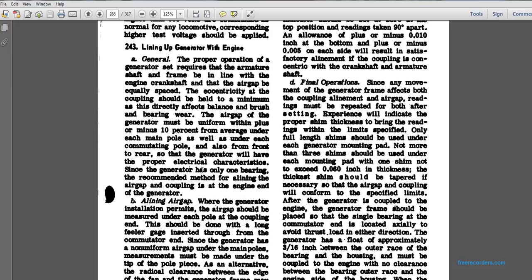Experience will indicate the proper shim thickness to bring the readings within the limits specified. Only shims of full pad length should be used, and each generator should be mounted on a pad. Not more than 3 shims should be used under each mounting pad, and no one shim should exceed 6/100 of an inch in thickness.